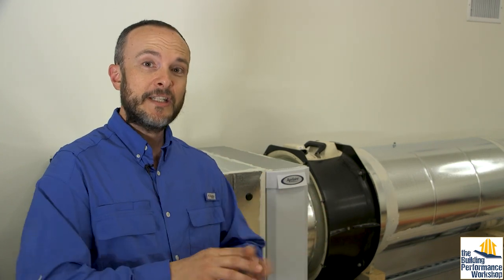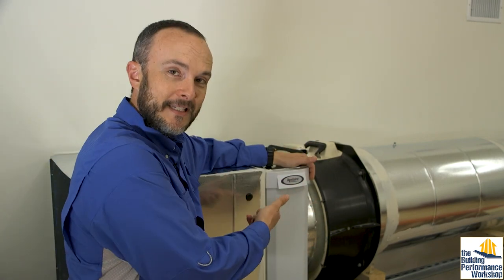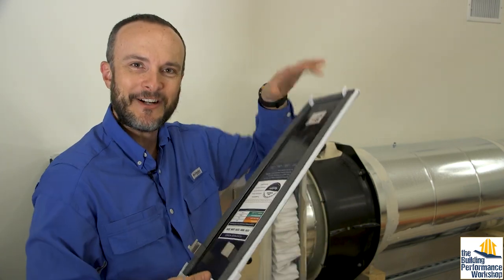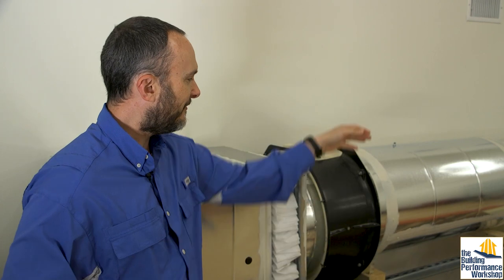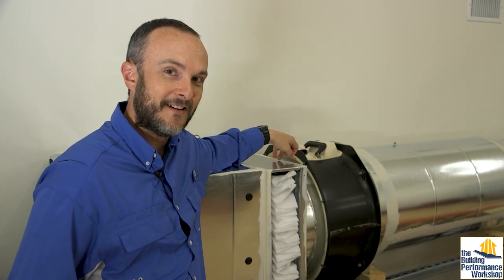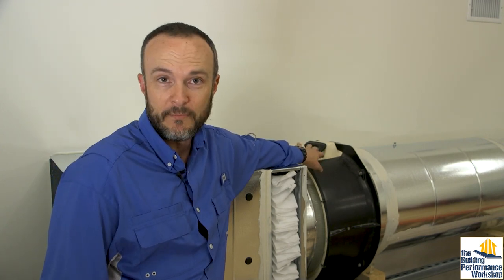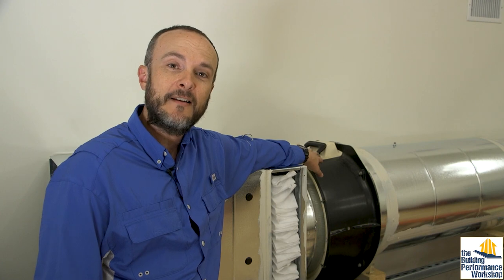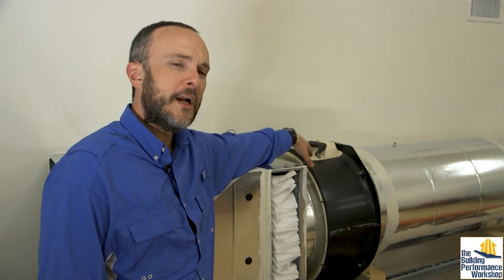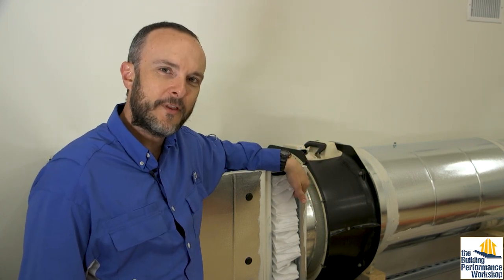You can use filters to take care of a lot of this stuff, but you're going to need to use different strategies. So what I've got in here, this is a filter box and you can see that it's got a gasket around it. This is incredibly important because if this was my air handling system, and this is my training system that I use at my training center here in Atlanta. Here is my pretend air handler, which is also called a blower. It's the thing that moves air in your circulation system of your air conditioner or furnace. And the pressure that it builds up, called static pressure, is highest right here before the filter.